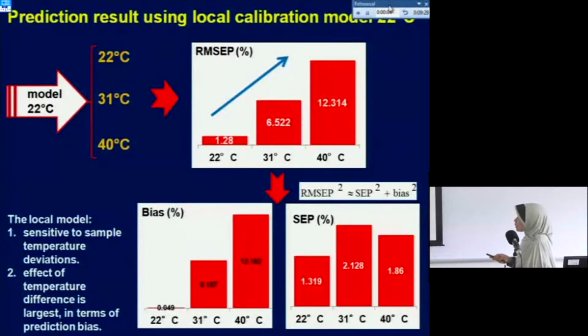Then the performance of the local calibration models was evaluated in the prediction step. First, using local calibration at 22 degrees Celsius, we can see that the total error of prediction gradually increases with increasing temperature. The local calibration at 22 degrees gives good prediction for samples at the same temperature, but the prediction was worse for samples at a different temperature. So from here we can see that the effect of temperature difference is larger in terms of bias, not SEP.